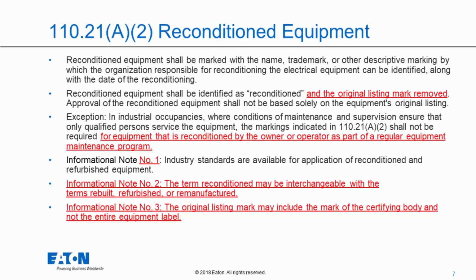They had informational note 2 that talks about... Sorry guys, I just had a little blip here of electricity. So I'm back on. Informational note 2 discusses that the term recondition may be interchangeable with the terms rebuilt, refurbished, or remanufactured. That was in there before. And the original listing mark may include the listing of the certifying body, not the entire label. And that's very important. Many manufacturer nameplates have the UL symbol on them as well. And so what they're saying is you could just replace the original listing mark.